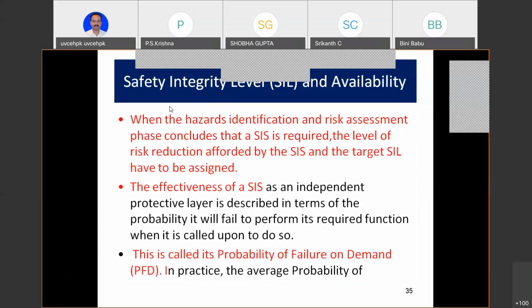Yeah, this one we have already seen, but I want to read it again. When the hazards identification and risk assessment phase concludes that a SIS is required, the level of risk reduction afforded by the SIS and the target SIL have to be assigned. It's very important for you to know because you have done it today for that small plant.